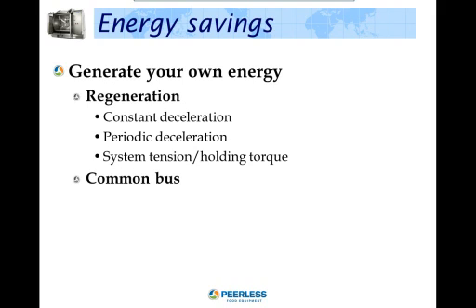The one question you should ask when trying to determine if the application is regenerative is, does the load at any time try to turn the motor, or is the motor being turned by the load? A common bus. When there are multiple AC drives in one location, a common bus system is usually the most efficient way to operate. It can incorporate the energy savings and recovery concepts that I have just discussed. If there is a regenerative AC drive and motor section in the system, it is ideally suited for maximizing energy recovery and cost savings.